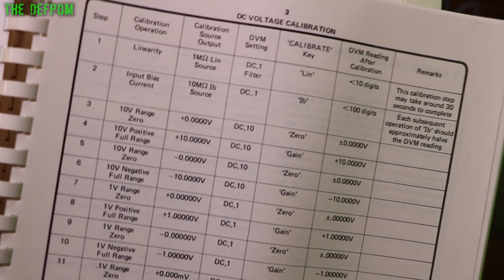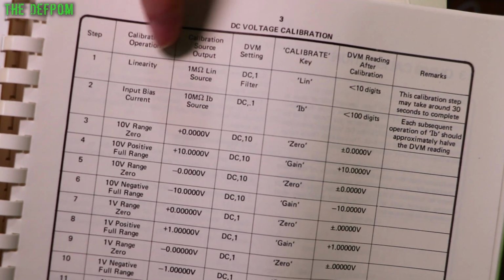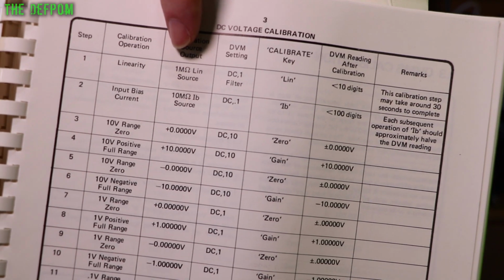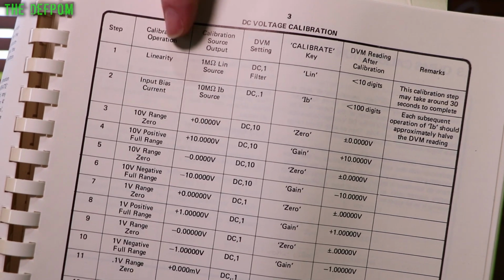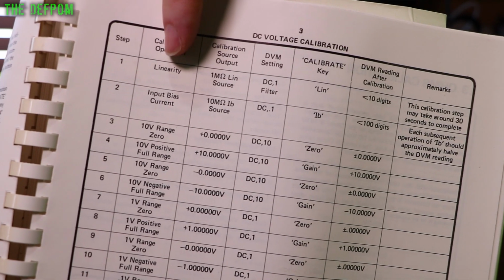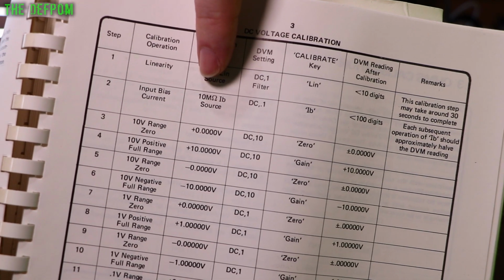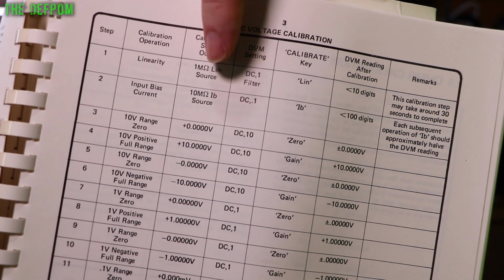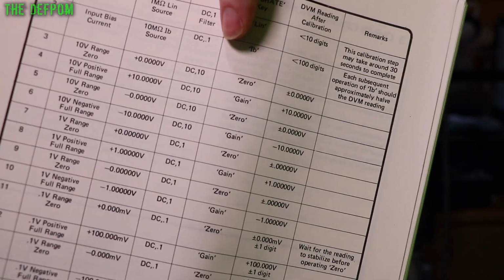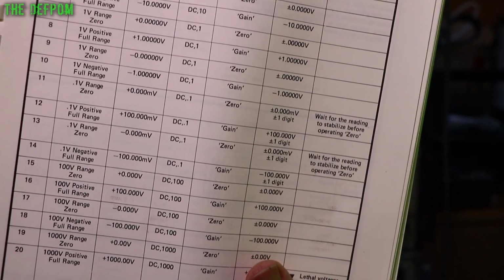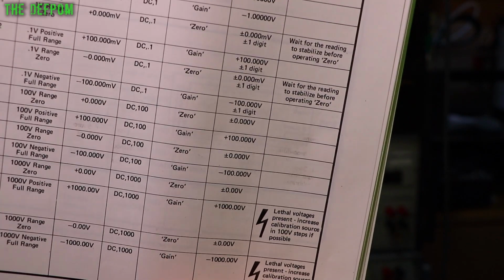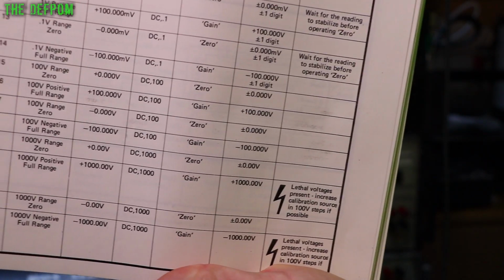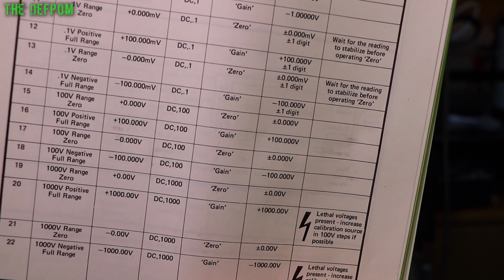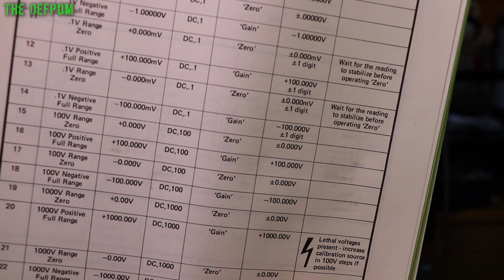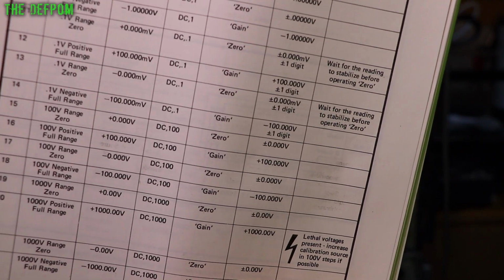So here's the page of the manual we've got to follow. You can see the first section here is the 1 megohm resistor, and the manual states that you use a 10 nanofarad capacitor with that in order to reduce noise. So the 1 megohm's fine, that one can work, and for 10 megohms we've got to inject the Fluke instead to try and get that right. Then we basically do the zeroing of each range, and then set up each range, up to 1000 volts. But the 1000 volts I can't reference against the HP because it can't do 300 volts max. So once I get up to that level, I'm going to have to use something else, but by then I think I'll probably stop recording because you get the idea anyway. It gets a bit boring after that. So I'll show you the first stages anyway.